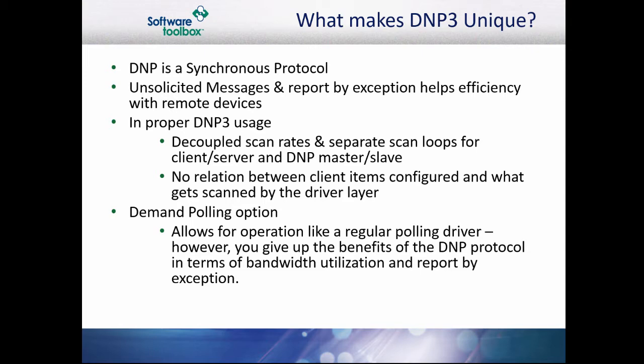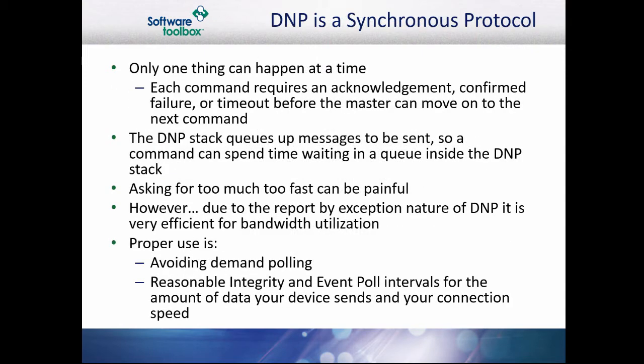DNP3 is a synchronous protocol requiring an acknowledgement, timeout, or confirmed failure for the current command before the next one in the queue is transmitted. The driver will often enqueue multiple commands within a typical DNP3 timeout period. The DNP3 stack must dispose of these commands in the order received. Outstanding commands for still-responsive slave devices can be blocked until the command queue empties, which in practice means that requesting too much data too fast can be painful.